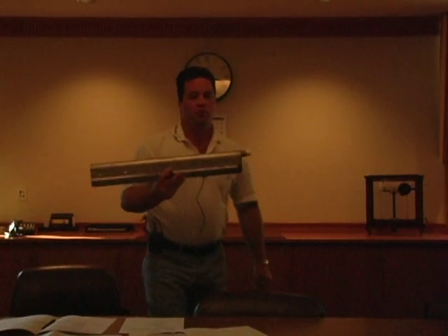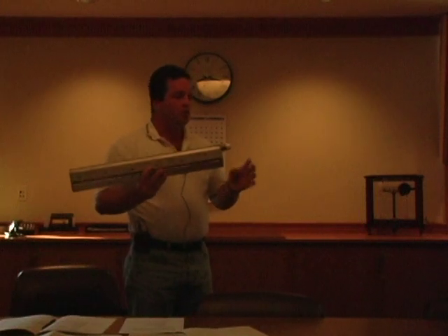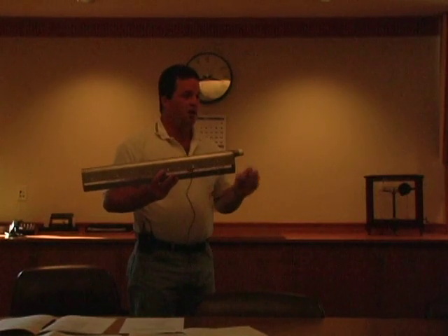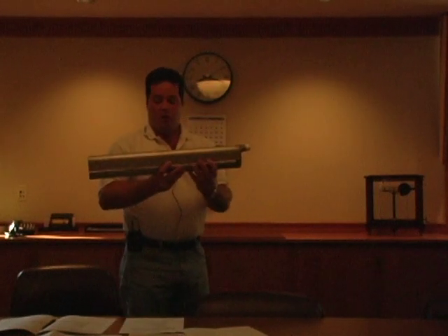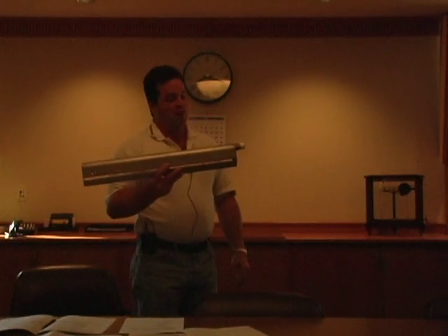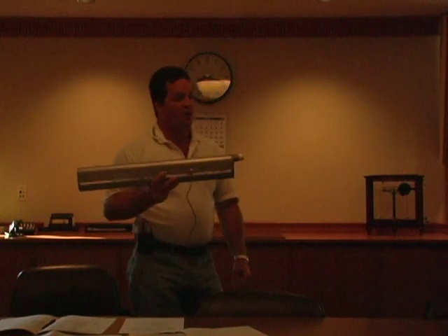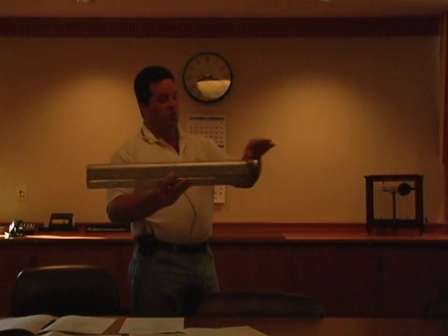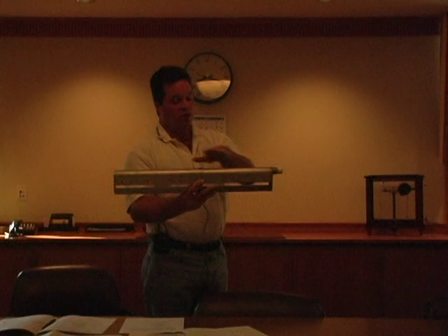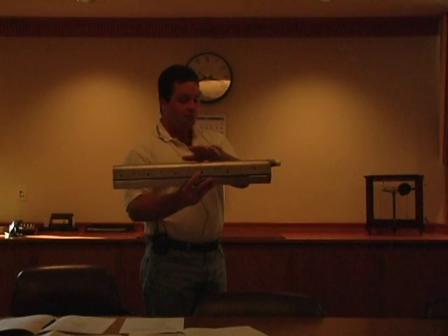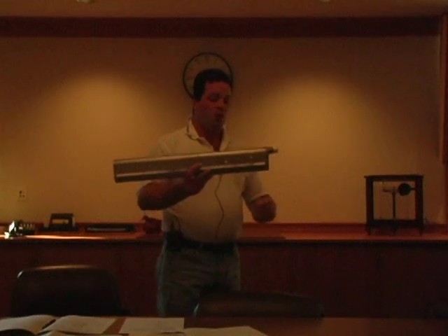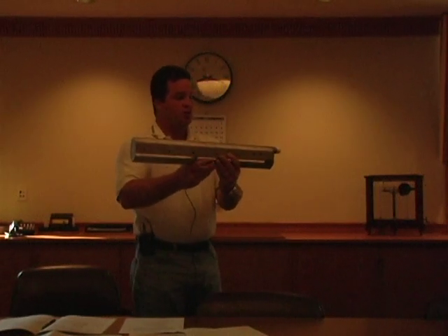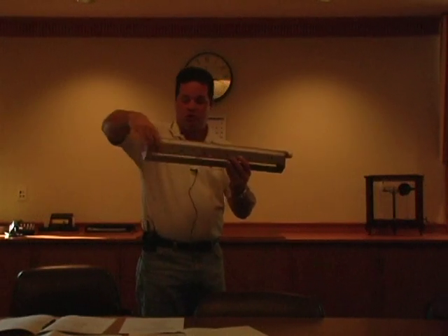What we're looking to do is get equal distribution throughout the channel and equal distribution throughout the header, okay? Basically what we want you to do from that point is you probably would put your plant effluent into the tank, and we want you to put the water just over the diffuser itself, okay? And then we want you to re-aerate the channel. What you can check at that point in time is just making sure that you've got equal distribution coming out of your diffusers, okay?